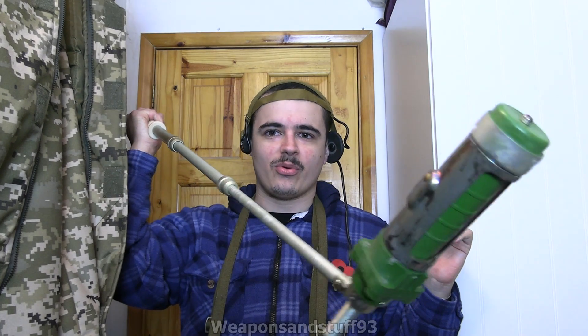Basically what I've got here is the extension wand with the probe. The idea is that although you can have this neatly tucked away, you can use it to measure samples further away from you without getting as close to contamination, and you don't have to keep bending over to measure samples on the ground. Here's the unit itself hanging off of me with the straps, and I've also got the headphones on so I can hear it ticking.